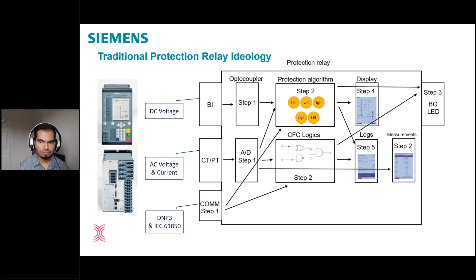So once it is processed in all these algorithms, then you have to get an output. An output is nothing but a result. The results of these outputs are pretty much processed data that is expressed by the relay through its HMI display, so your LCD display on the relay, through binary outputs, through LEDs, or stored in various logs, and also communication back to the control center or the other relays by using the communication port. So that's your normal traditional protection relay ideology.